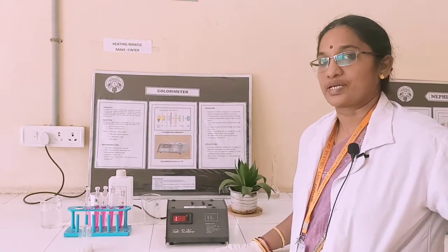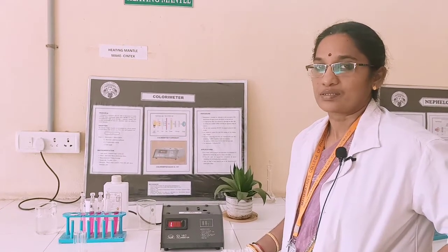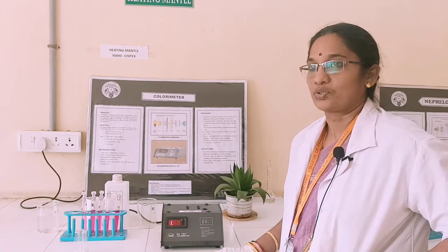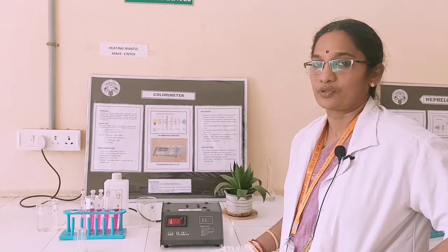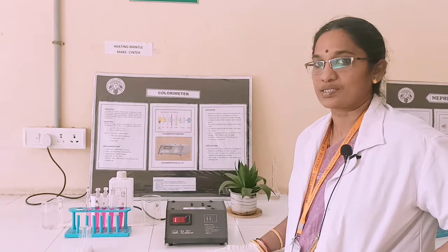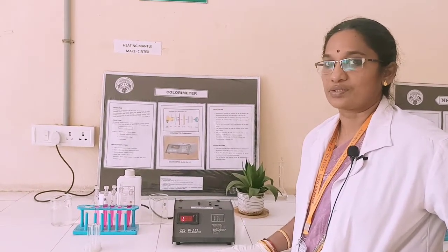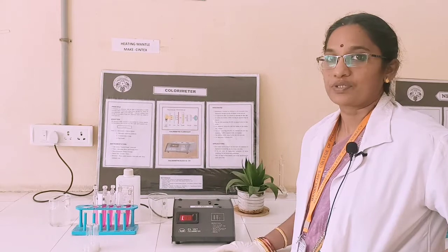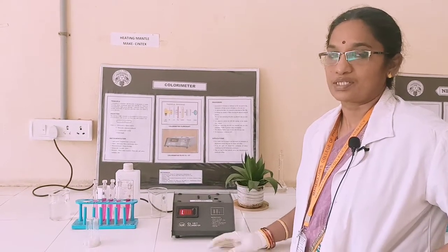After the light source, the second part is a monochromator. The name monochromator: monochroma indicates single color. That means monochromator is a part of the spectrophotometer that cuts off the unnecessary wavelengths and passes the single wavelength or the necessary wavelength range into the sample. Monochroma, single color and single wavelength. This is the basic purpose of the monochromator that is present in a spectrometer.